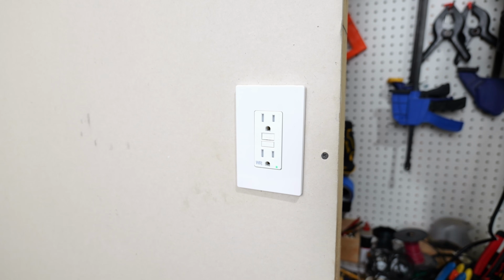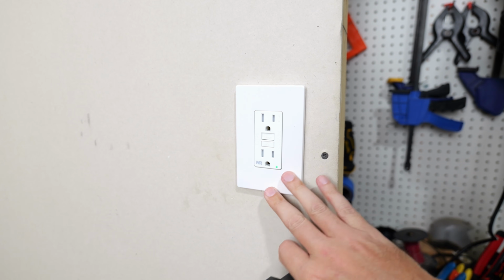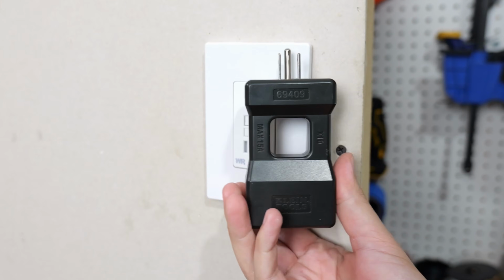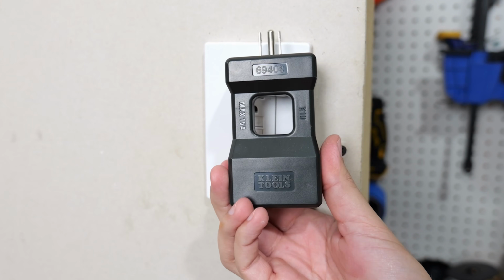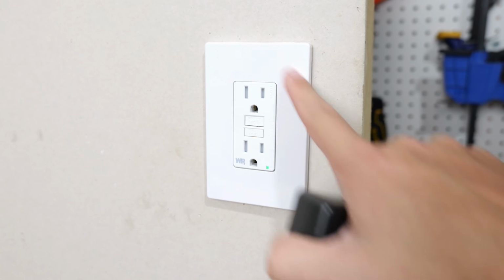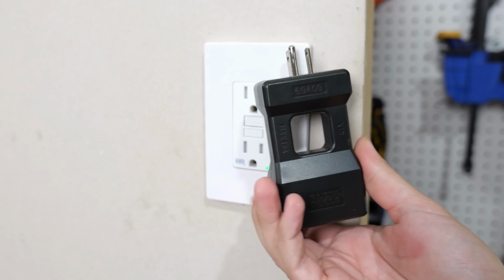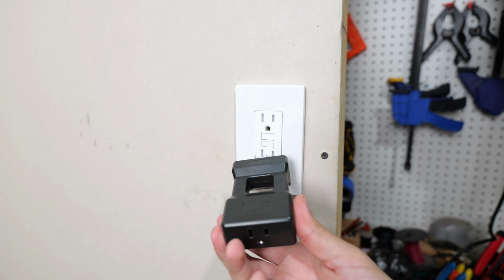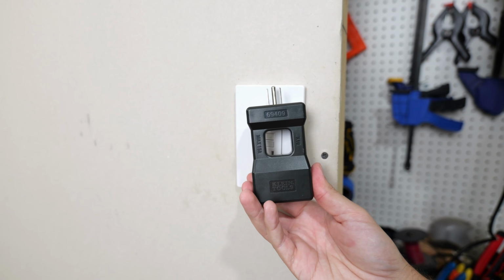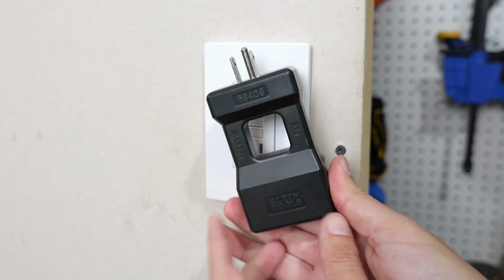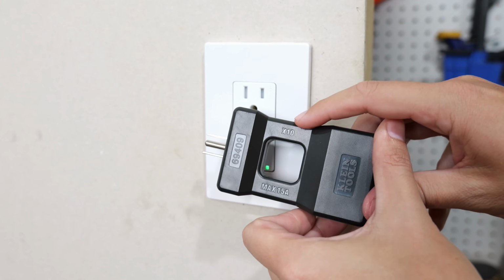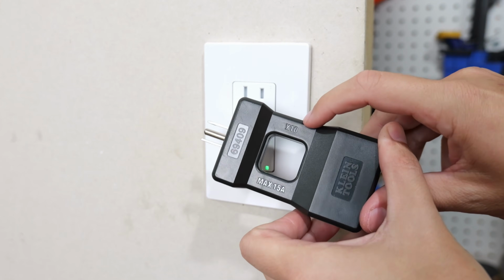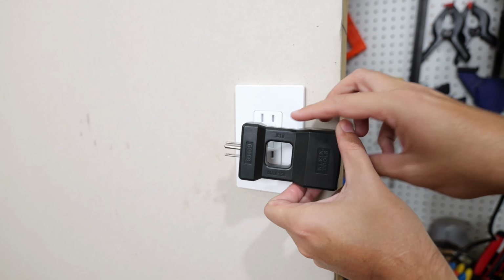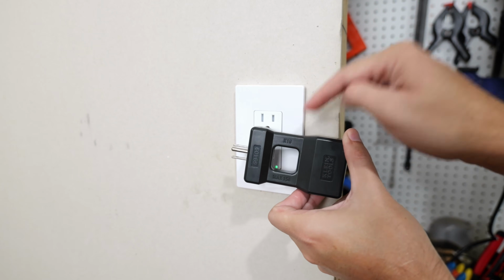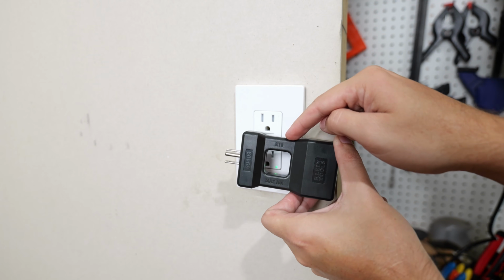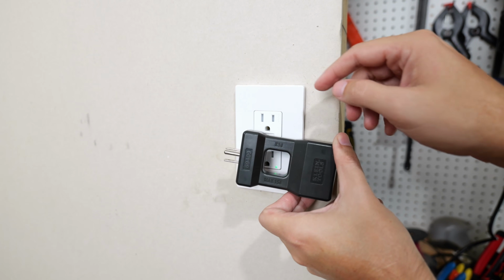Another great way to check this with the clamp without having to take any of this apart is by getting one of these splitters right here. This one in particular is made by Klein. As you can see, we've got our cover plate on and everything, so we're not inside the box, but this splitter just gets plugged into the receptacle and we can get our reading that way. Some very important information to note before we do this: you'll see right here on the side, this is our hot side, this is where we're going to take our measurement. It says times 10, meaning the reading I get on my screen will be 10 times the actual amperage amount running to whatever I'm trying to test.